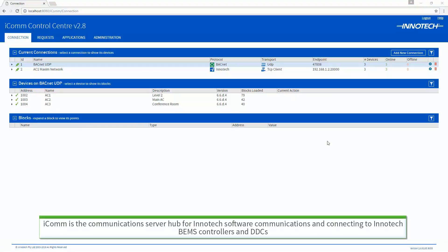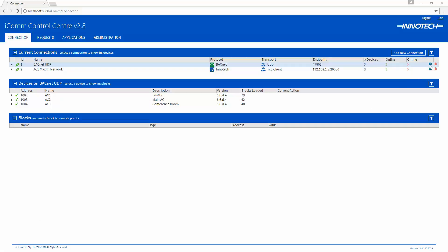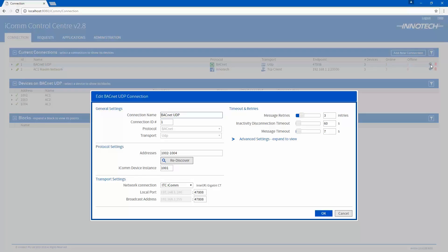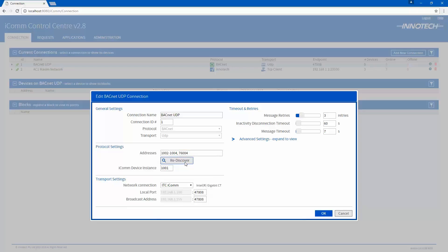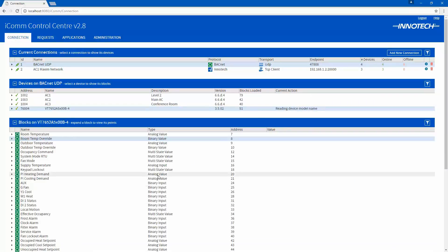Next, we can edit the BACnet UDP connection in ICOM to discover the added MSTP devices. Click the Edit icon to open the connection properties. Click the Rediscover button to locate the device. The BACnet MSTP device will then be added to the address list, as Omni automatically routes the MSTP link to the BACnet IP network. Click OK to save the changes. The device will then be listed under the BACnet connection.